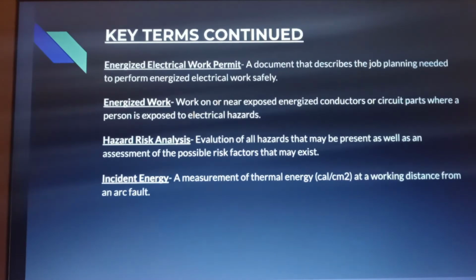These next few key terms are pretty important later on. So, energized electrical work permit: a document that describes the job planning needed to perform energized electrical work safely. And then energized work is obviously work on or near exposed energized conductors or circuit parts where a person is exposed to electrical hazards. Hazard risk analysis is the evaluation of all hazards that may be present, as well as an assessment of the possible risk factors that may exist.